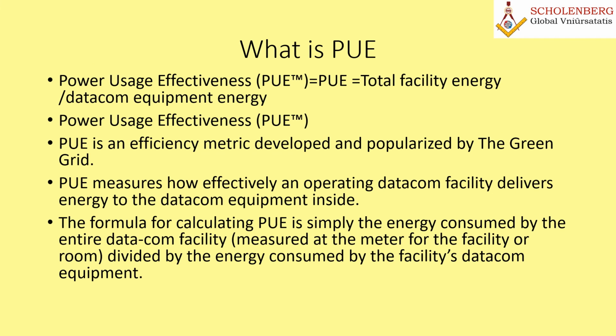The second most important term in data center design is PUE. What is this PUE? It is an efficiency metric developed and popularized by the Green Grid. Since the concept was introduced by Mr. Rawson in 2007, the metric has been revised to make reporting the measurement more understandable and the numbers more reliable. PUE measures how effectively an operating datacom facility delivers energy to the datacom equipment inside.